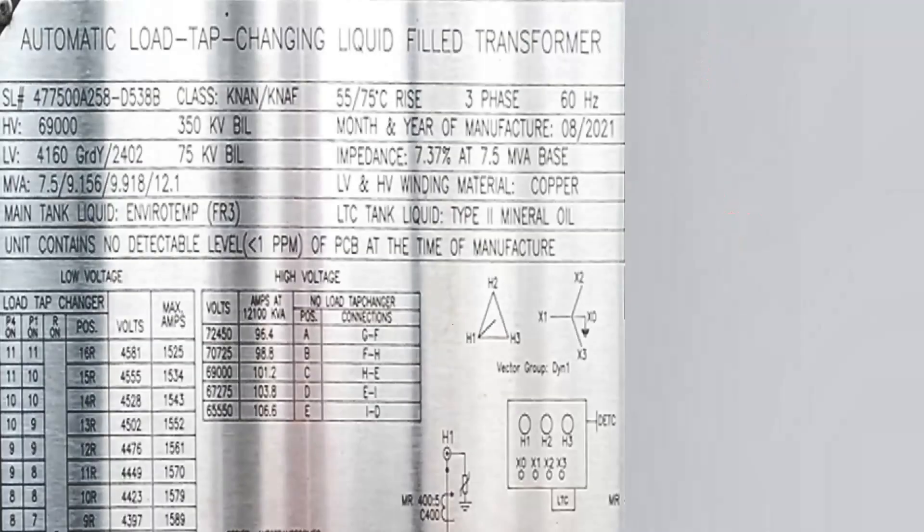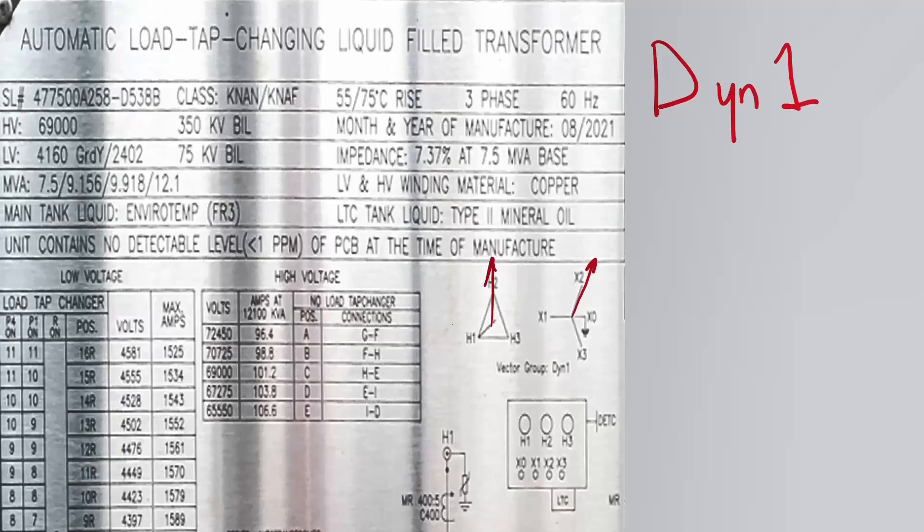Let's look at another one. And this one right here is one of the more common ones. And they even gave us our vector group, so we're just going to confirm that using this same logic. And here it's a delta, so this is a big D. And then we have a Y with an accessible neutral on the secondary. So remember, we don't need the clock for the primary. So this is going to be a Y,N. And then what's our clock shift? Well, if H2 is directly up, as you look at that, where is X2? Well, it's at 1 o'clock. So that puts this at a D,Y,N,1. And lo and behold, that's exactly what they got there.